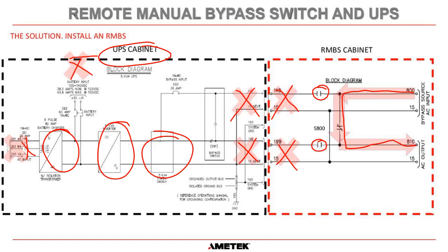And in truth, what you can actually do is disconnect this cable here, all the input cables and the battery cables, and you could remove the UPS if it's an old UPS, and then you could install a new UPS and then reconnect all those cables, and then eventually, using the RMBS cabinet, power the load back from the UPS. So during all of this, the loads are still being fed from our bypass source here out to our AC output. So the plant does not need to take an outage to do that, which is absolutely fantastic.